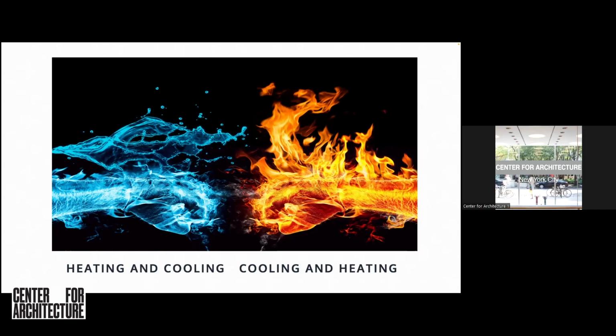Even if the facade is a good facade, there's always leaks in the building: loading docks, service doors, entrances that don't have properly designed vestibules. These are all sources of air leakage, and they can be substantial. And when cold air gets into a warm building and warms up, the heat rises and it creates suction that pulls more and more air in from those leaks. And it shows up as front doors that are hard to open and close, whistling in elevator lobbies, elevators that make tremendous amounts of noise when they go up and down, elevators that have problems with the doors opening and closing. These are all very common problems that we see in high-rise buildings that have excessive air leakage.